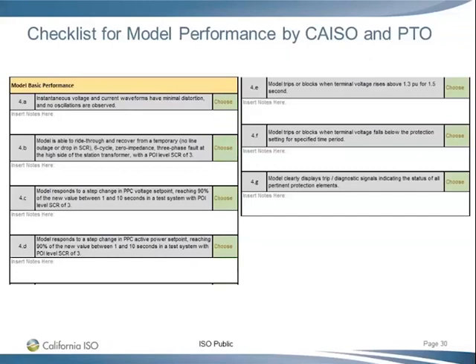So we are going to look for the protection settings. You submit it as the overall package. So that's also in the positive sequence model. Then in the test we will make the voltage fall below that threshold, and then for a certain time that will exceed your protection setting. Then we are expecting to see that the generator is tripped. So this answer should be yes.